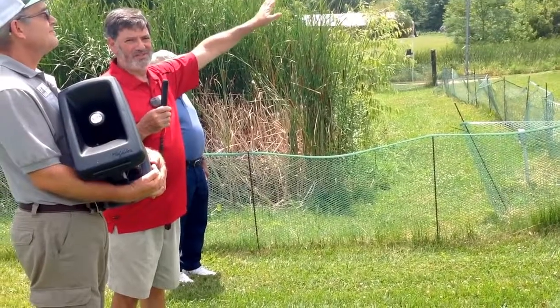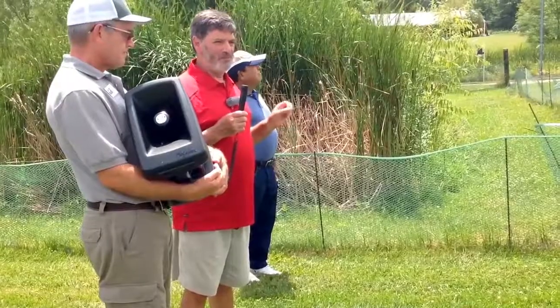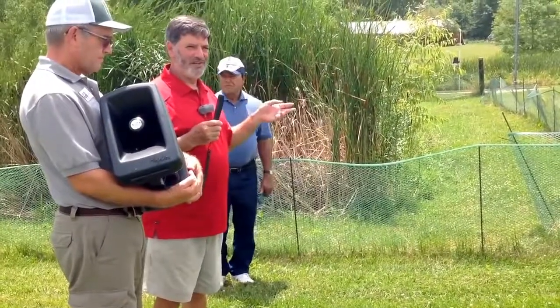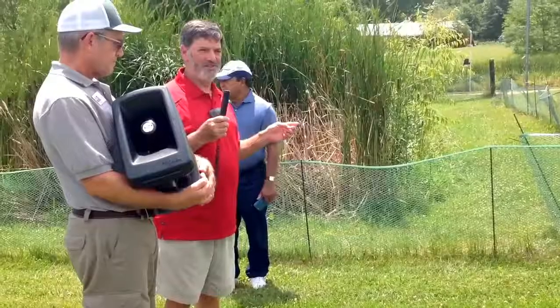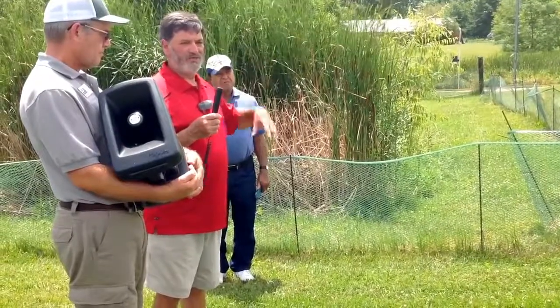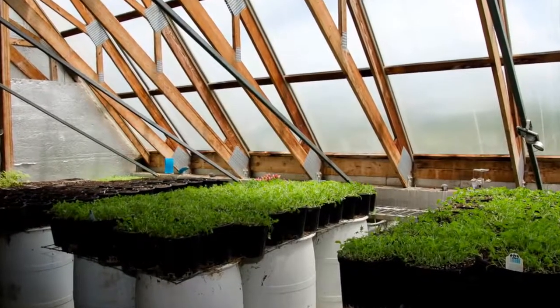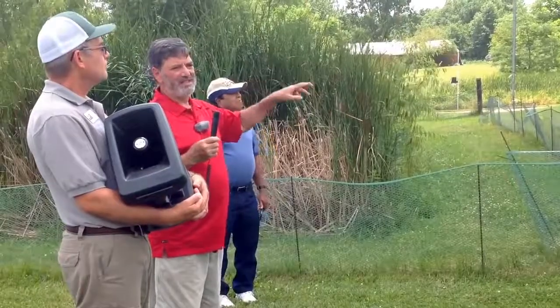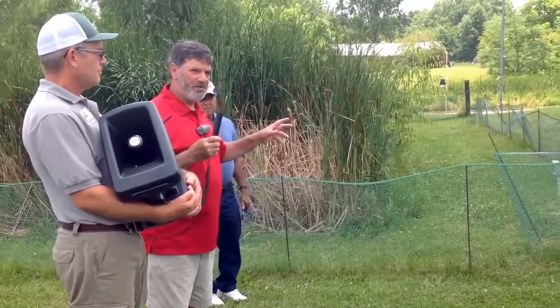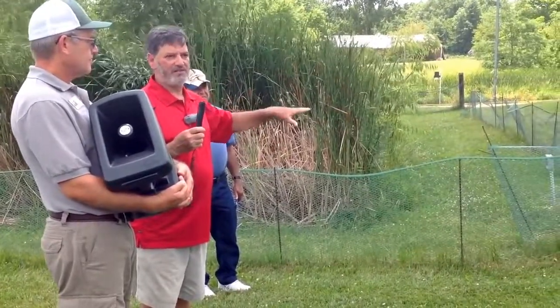These are solar thermal collectors. I have a hot water drain-back system. I originally started with a propylene glycol system, but it was letting air in the lines and the copper was starting to degrade. Another guy with more experience said to get the propylene glycol out and just use straight water, and it's worked fine ever since. At 34 degrees everything drains back into the building so the pipes don't freeze in winter. This is hooked into a heat exchanger that pumps the hot water into a storage tank, and when that storage tank reaches a certain temperature, PEX tubing in the concrete floor allows the floor itself to act as thermal storage.